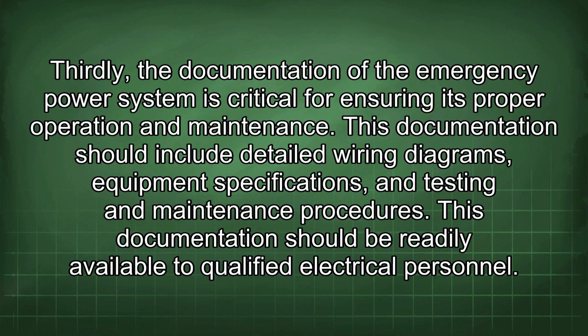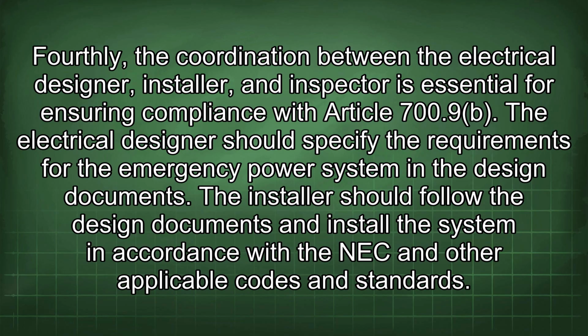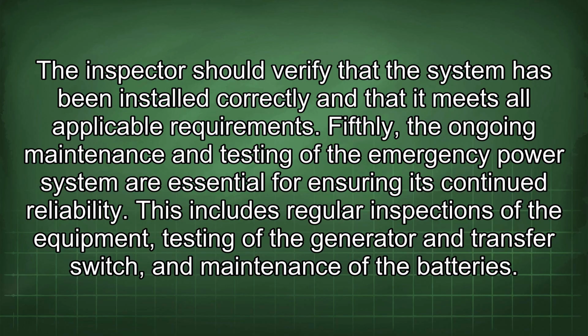Thirdly, the documentation of the emergency power system is critical for ensuring its proper operation and maintenance. This documentation should include detailed wiring diagrams, equipment specifications, and testing and maintenance procedures. This documentation should be readily available to qualified electrical personnel. Fourthly, the coordination between the electrical designer, installer, and inspector is essential for ensuring compliance with Article 700.9. The electrical designer should specify the requirements for the emergency power system in the design documents. The installer should follow the design documents and install the system in accordance with the NEC and other applicable codes and standards. The inspector should verify that the system has been installed correctly and that it meets all applicable requirements.